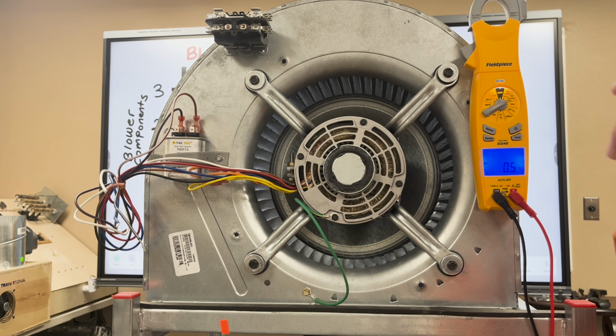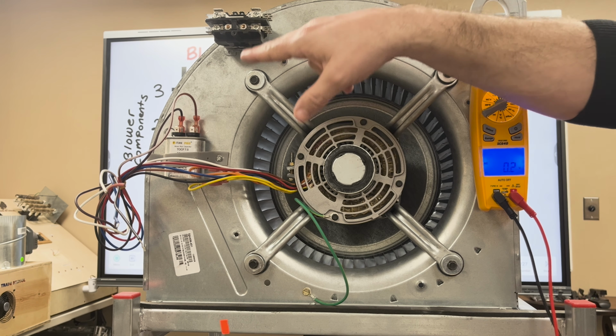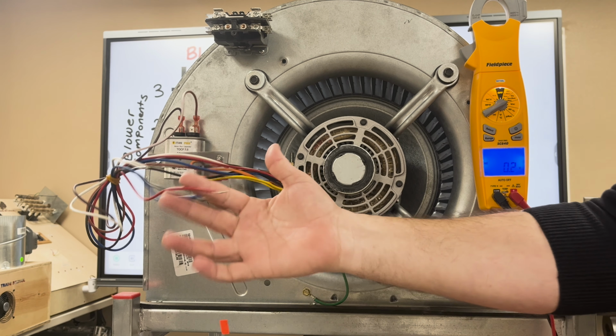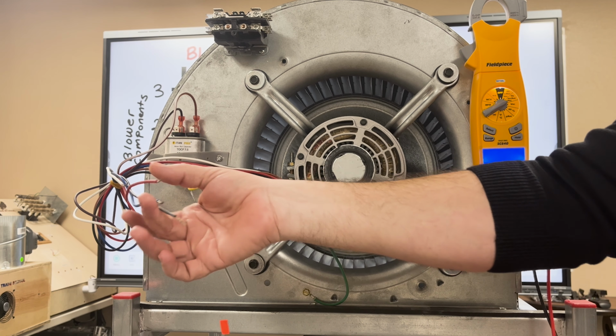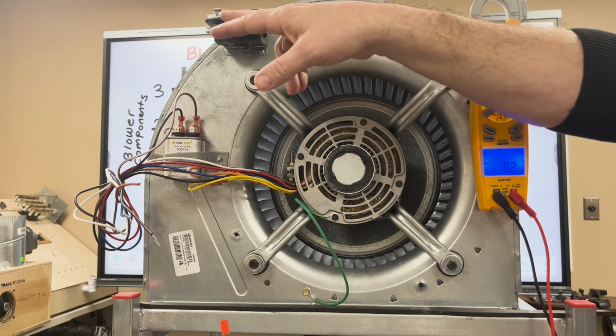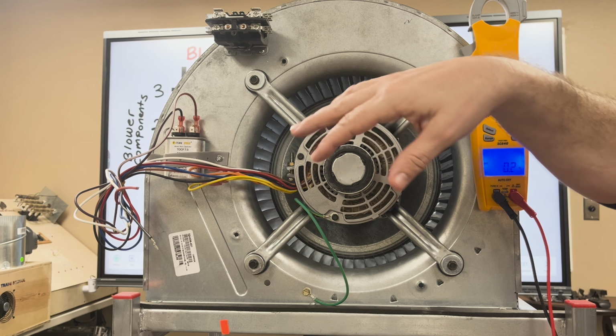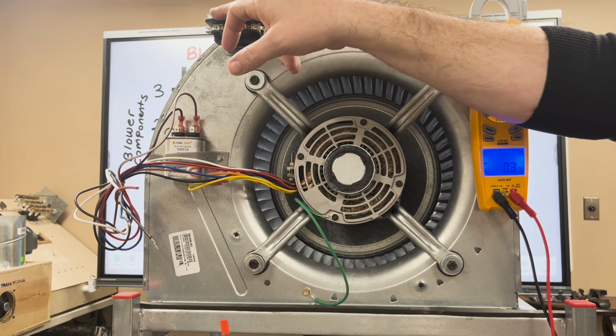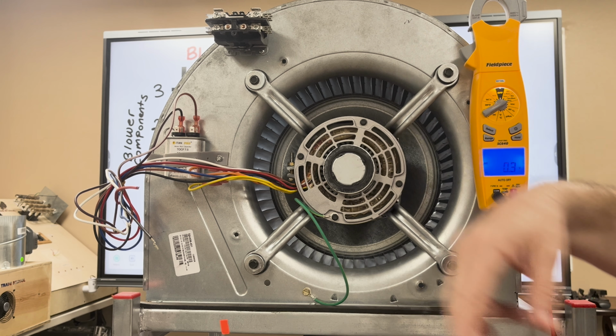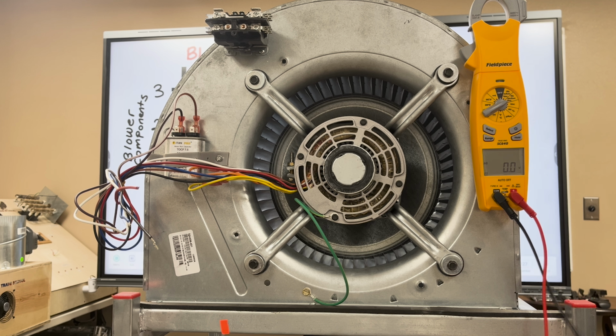Just using one lead inside of here, I should be able to leave that in there so I can show you how there's still power present on all these other speed taps when the relay is in the open position, not allowing the motor to come on, because we're only breaking one side, the other leg's going to be present all the way through. I really want to demonstrate that. I think that's a confused thing in our industry, that I don't think we dive enough into it to get that respect.